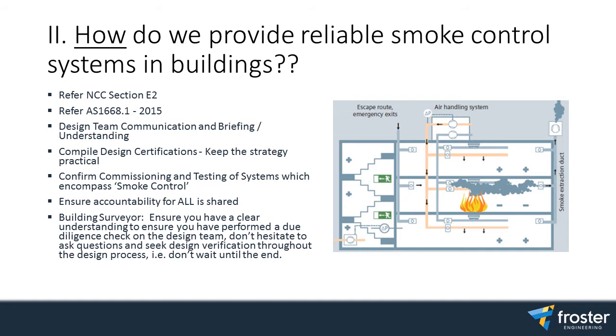We want to look at working together as a team. We've talked about it a few times already. Compile design certifications from the relevant consultants, from the fire engineer and the mechanical consultant. Confirm commissioning and testing has been provided at the end of the construction. Ensure accountability is shared, and for the surveyor, you want to make sure you have an understanding. And you ask questions of everyone on the project, especially me. Make sure I know what I'm talking about. Make sure I have the design correct, and make sure that you're familiar with it. So when you're on site, witnessing a test or doing an inspection, you have perspective.